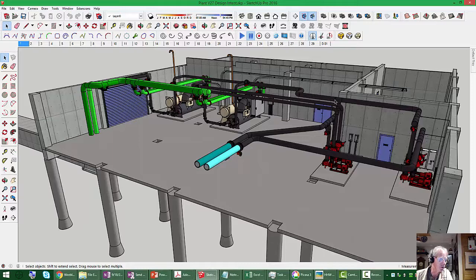There'd be a control valve in it because even in a variable flow primary only plant, you can't let the flow to the chillers drop below a minimum safe level. So there has to be a mechanism in place to keep minimum flow up to the plant. That's not always in the central plant. Sometimes it's out at the end of the system. There's different design philosophies about that. But that'd be another clue.